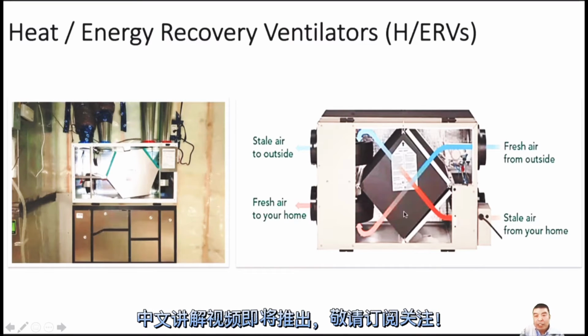This heat exchanger is like a furnace heat exchanger: this air and this air are not mixed. If they mix, that means the heat exchanger is broken inside and needs to be changed. This other side is the stale air from your home. For a new house, we run the pipes to the washroom, sometimes the kitchen, and sometimes the living room. They just suck the stale air from there, it goes through the other side of the heat exchanger, and then blows out.